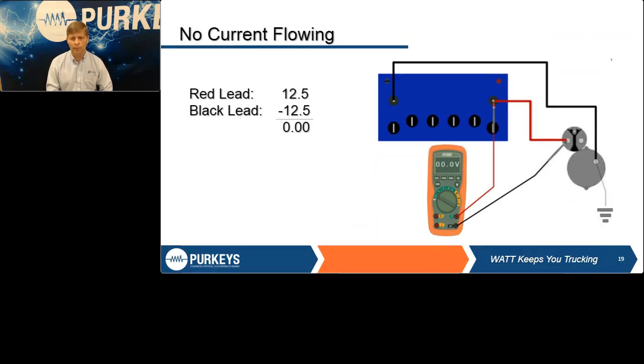Now, people always want to use a voltmeter with red on positive and black on negative. Can I use a voltmeter positive to positive? The answer is yes. In this example, I've got my red lead on battery positive and my black lead on starter positive. What do I read at the battery? 12.5. What do I read at the starter? 12.5. What's the difference? The answer is 0. The key right now is that no current is flowing. If I don't have current flowing, I can't have voltage drop.